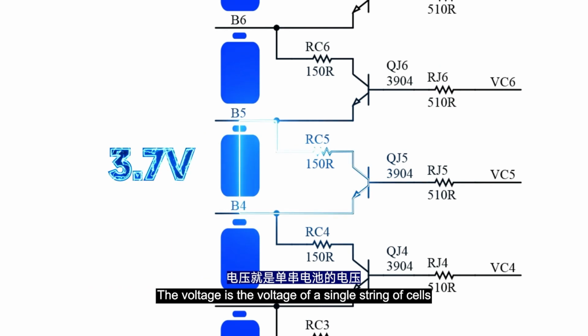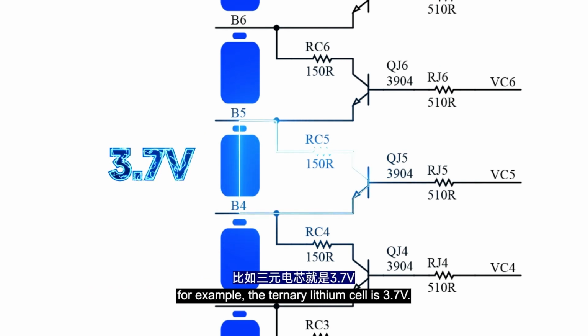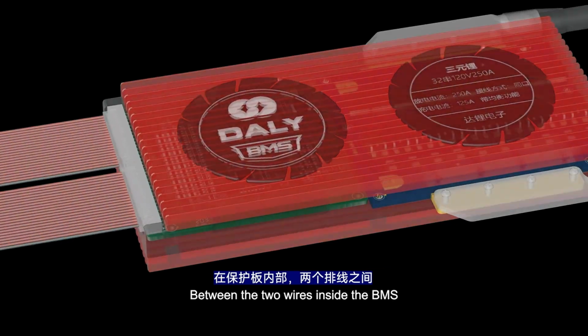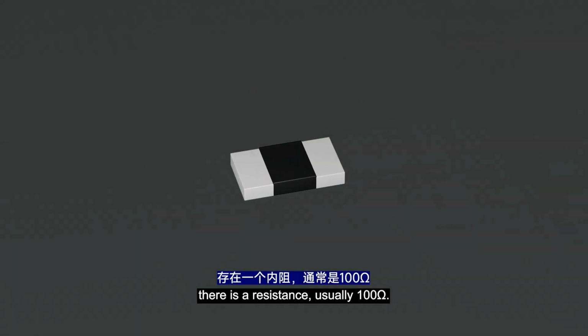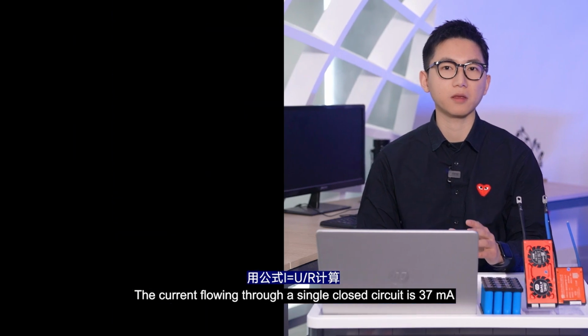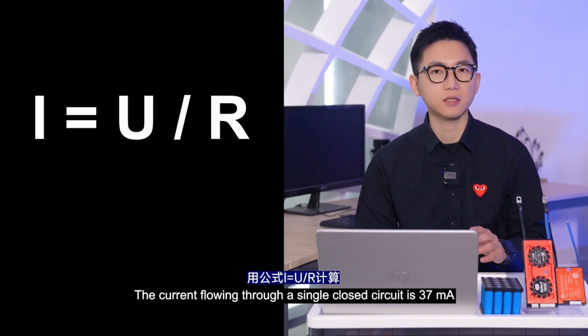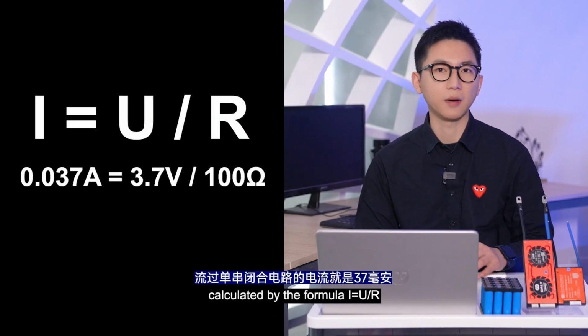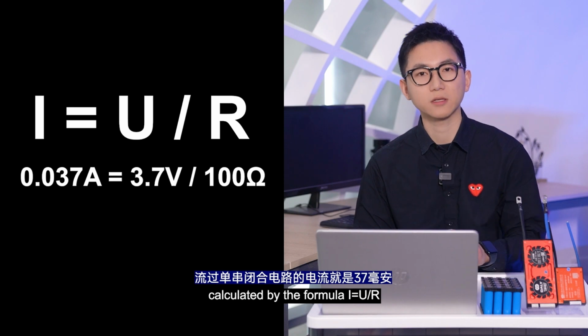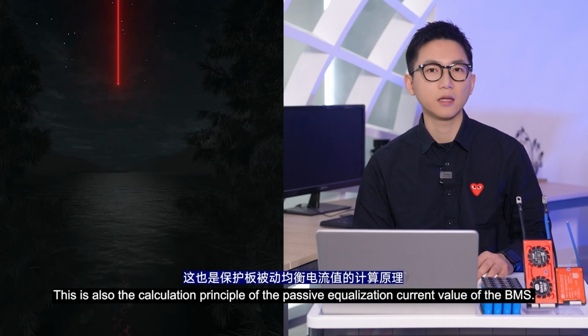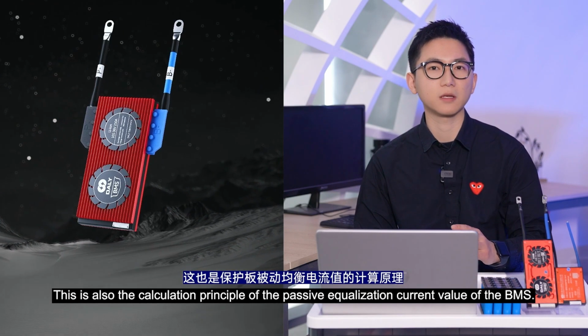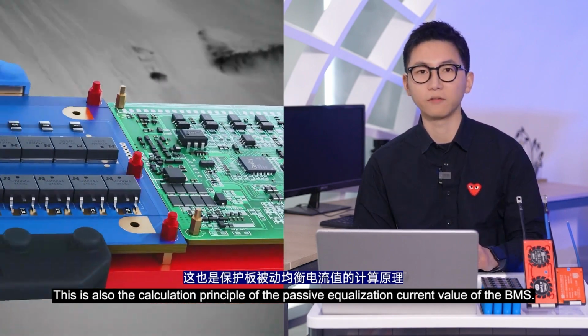The voltage is the voltage of a single string of cells. For example, a single lithium cell is 3.7 volts between the two wires inside the BMS. There is a resistance, usually 100 ohms. The current flowing through a single closed circuit is 37 milliamperes, calculated by the formula voltage divided by resistance equals current. This is also the calculation principle of the passive equalization current value of the BMS.